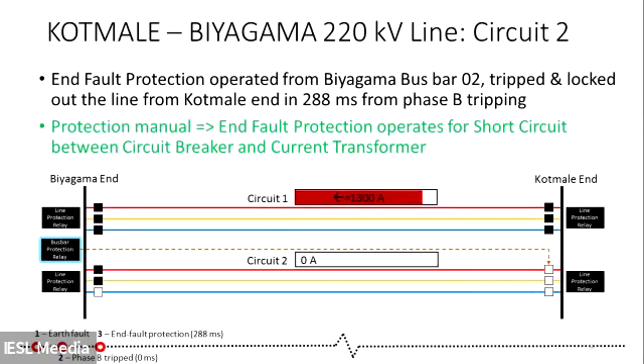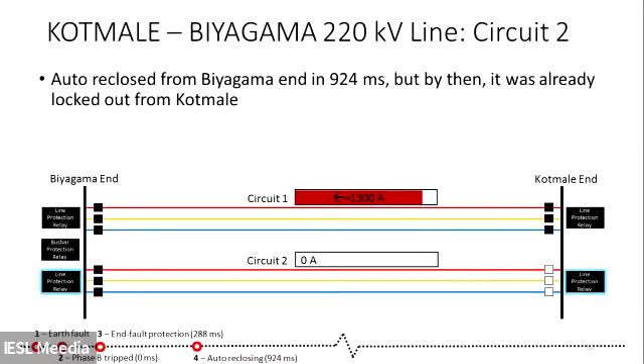Typically, the protection manual says that the end-fault protection operates for a short circuit between the circuit breaker and the transformer. So this is some other phenomenon which took place during that time. With that, the current in circuit 1 increased to 1,300 amperes, still within the limits because the circuit is rated at 1,500 amperes. So with circuit 2 lost, the system still continued after some transient. Then, of course, the auto reclosure of circuit 2 happened, but the only thing is that because of the end-fault protection operation that took place previously, at the Kothmale end, thank you.